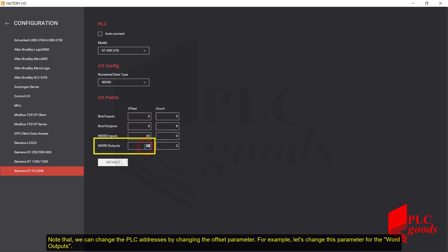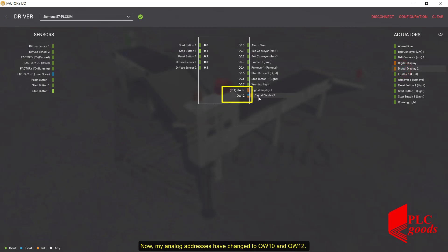Note that we can change the PLC addresses by changing the offset parameters. For example, let's change this parameter for the word outputs. My analog addresses have now changed to QW10 and QW12. Remember, each word address includes two bytes — in other words, 16 bits.